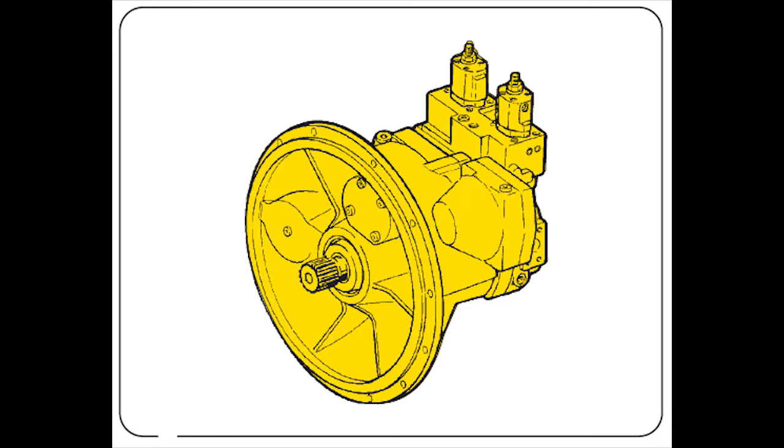The flow is proportional to the input speed and to the displacement, and is infinitely variable from QV max to QV min. The pump is suitable for direct mounting on the flywheel case in diesel engines.